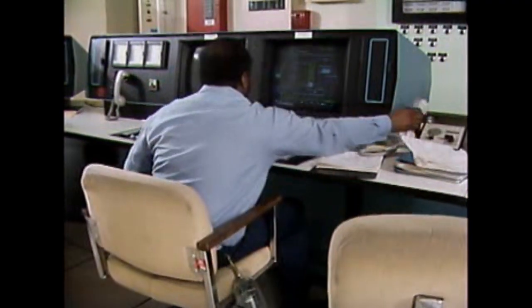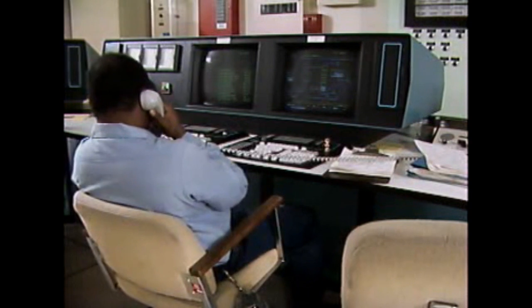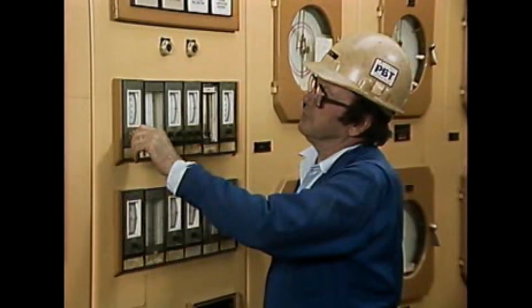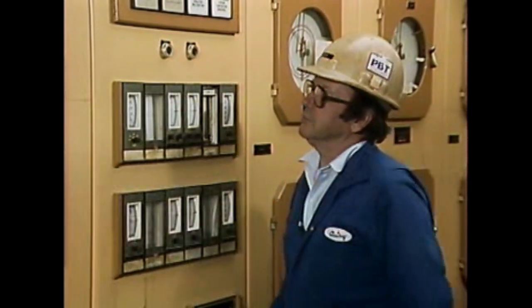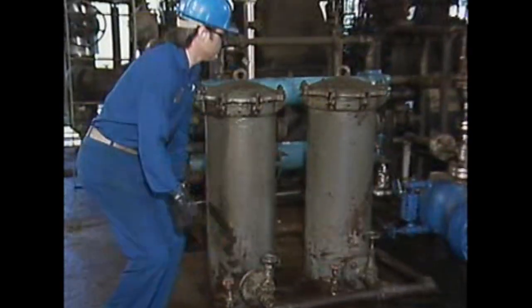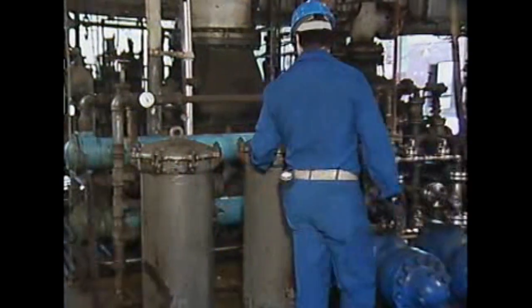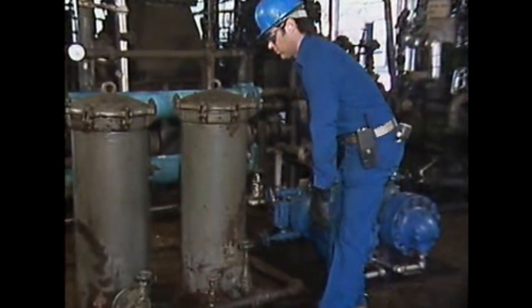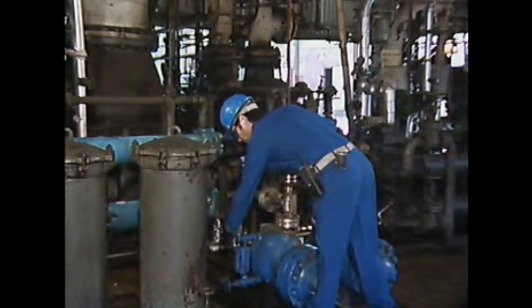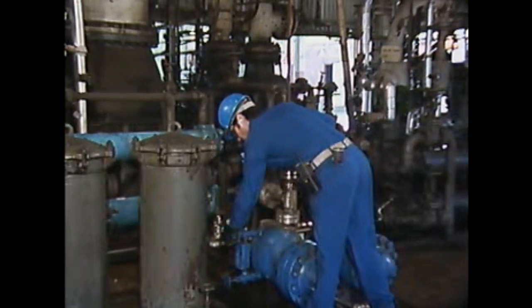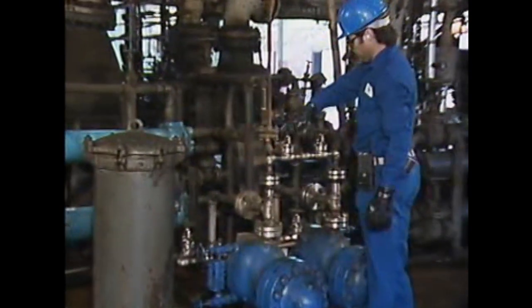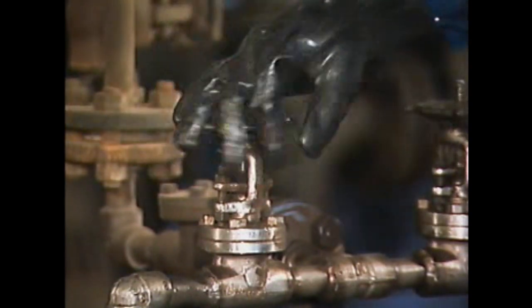Before the compressor can be started, operators must verify that the compressor's gas supply is available and that the controls are set in the proper positions. Another important part of preparing a compressor for startup is performing what's called a valve lineup, which means making sure that all of the valves associated with the compressor and its auxiliaries are in the proper positions. For example, this operator is opening the oil supply valves in a compressor lubrication system.